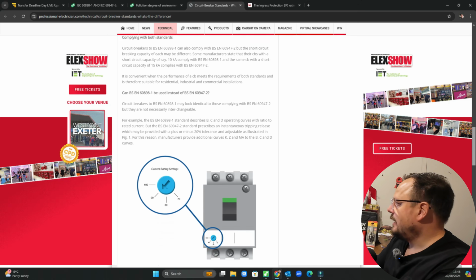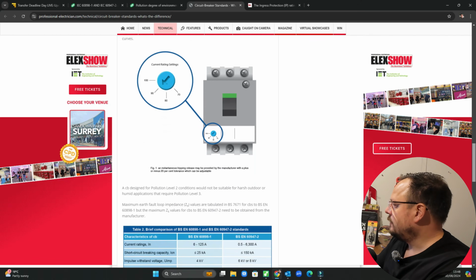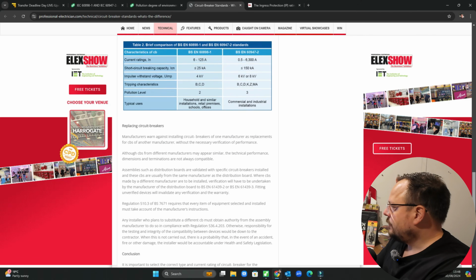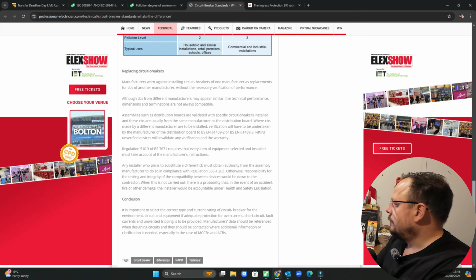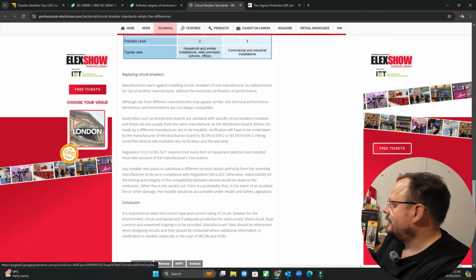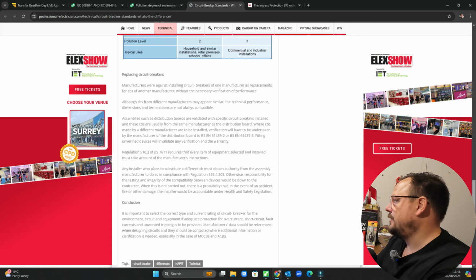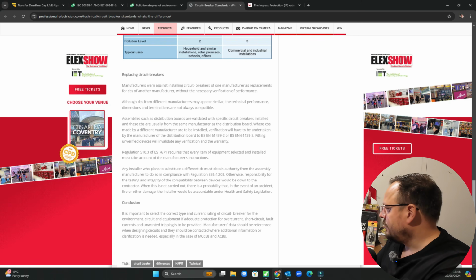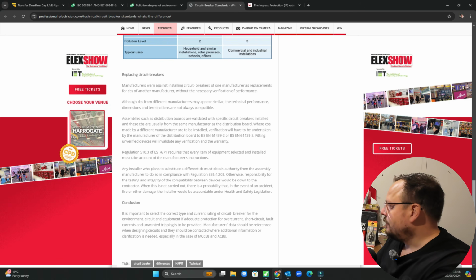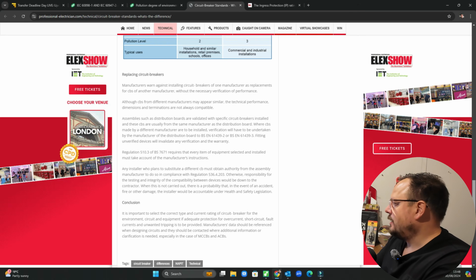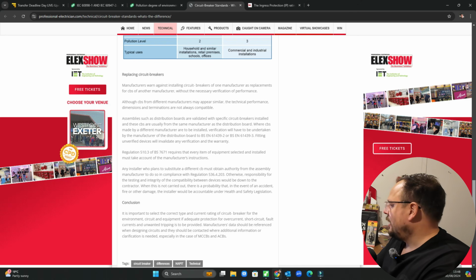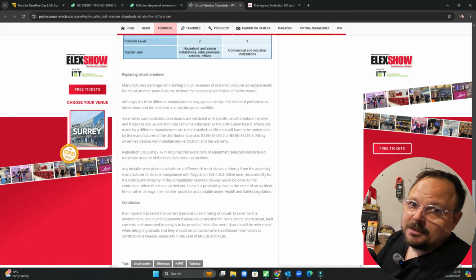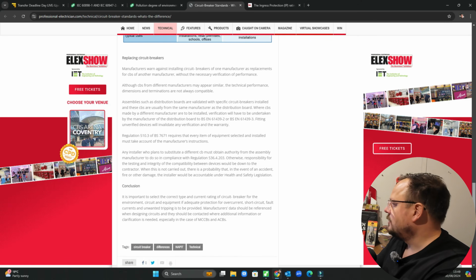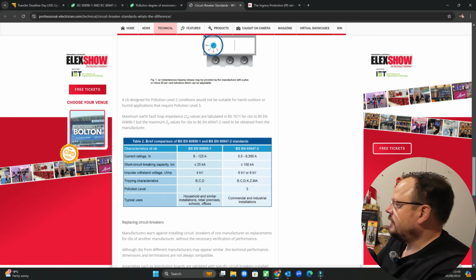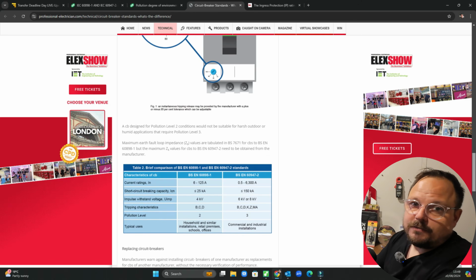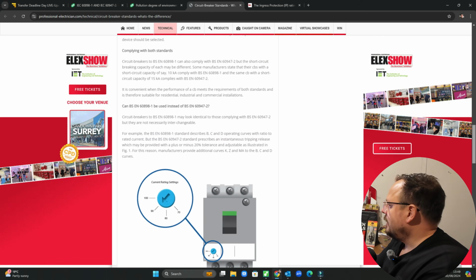They can look identical, so it's worth checking the numbers on the front. And again, as we scroll through there, it goes on to talk about replacing circuit breakers. Manufacturers warn against installing circuit breakers of one manufacturer as a replacement for circuit breakers of another, so it's covering that as well. The conclusion is it's important to select the correct type and current rating of a circuit breaker for the environment, circuit and equipment. There's loads of chat in and around there, and it mentions MCCBs as well. There's loads of different tools in the box in terms of overcurrent protective devices, and they all exist to cover off different requirements. So yeah, there we go on that one.